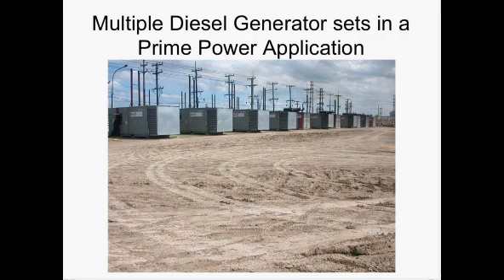Most diesel engine-driven generator sets are used for standby power or standby power with occasional utility curtailment plans. I will now show some examples of standby power. Many of these applications are rated prime power, so the owners can use the generator sets for more than just standby. This can generate revenue or lower electrical costs for the facility. It is an exercise in engineering economics to decide when a diesel engine generator set may be used for a dual purpose. The higher installation cost and higher maintenance cost have to be weighed against the benefit of the revenue generated from the utility program. This is different for every installation.